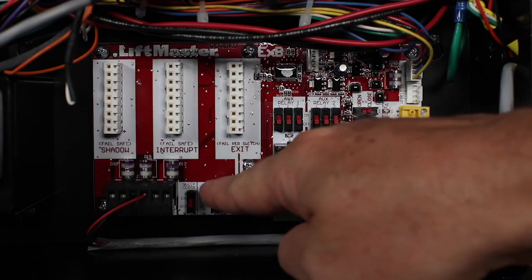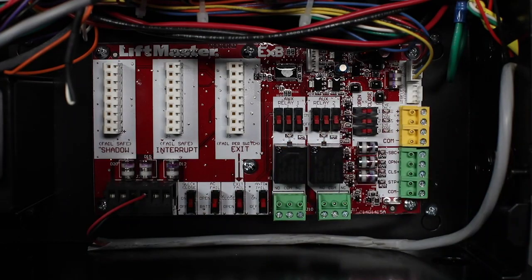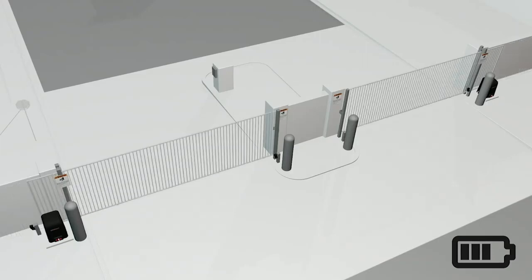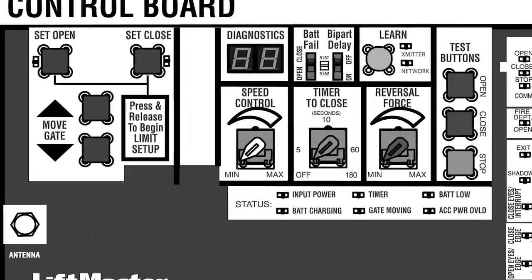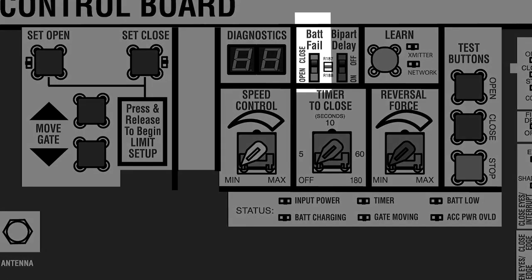Setting the AC fail switch to bat will cause the operator to run on battery power. As the battery voltage approaches the critical low of 23 volts, the operator will beep 3 times when a command is given to move the gate. When the voltage drops below 23 volts, the bat fail switch determines what the operator will do.